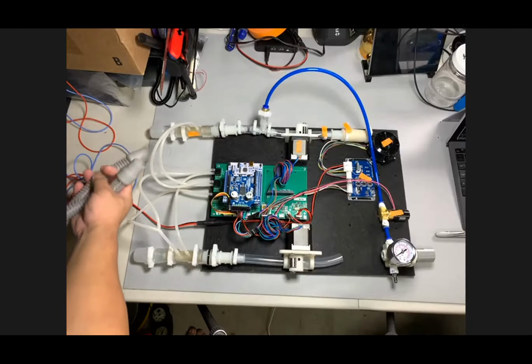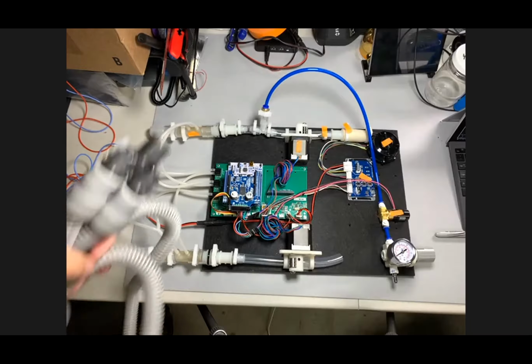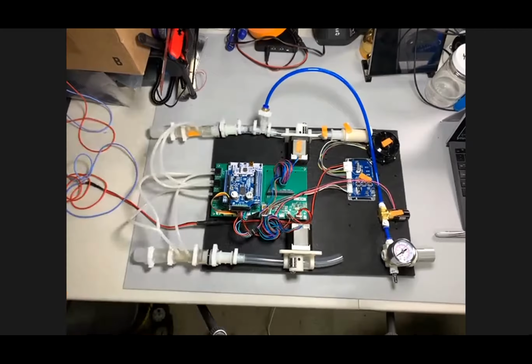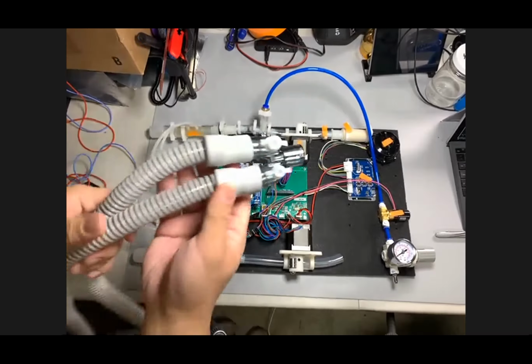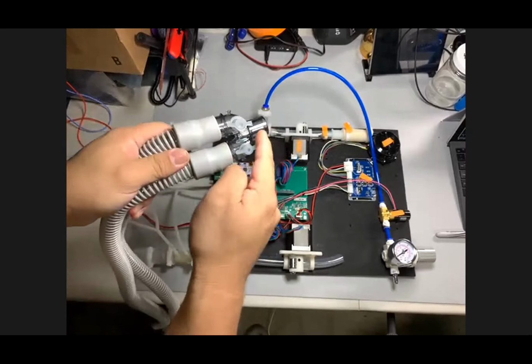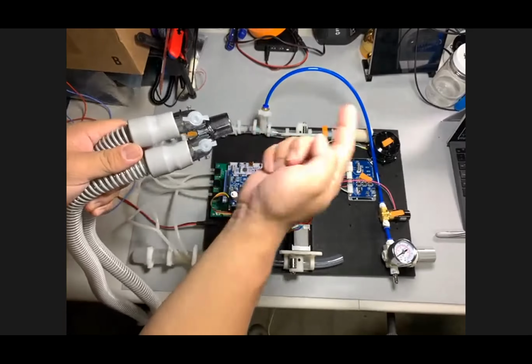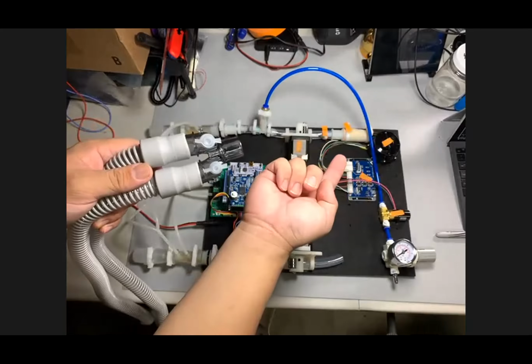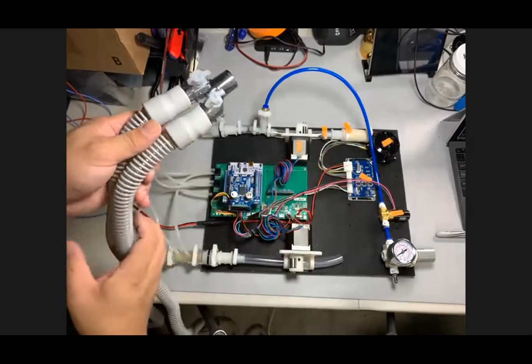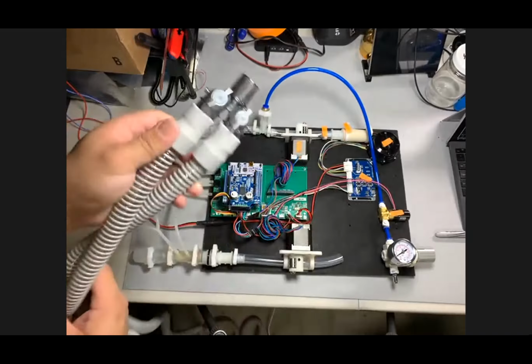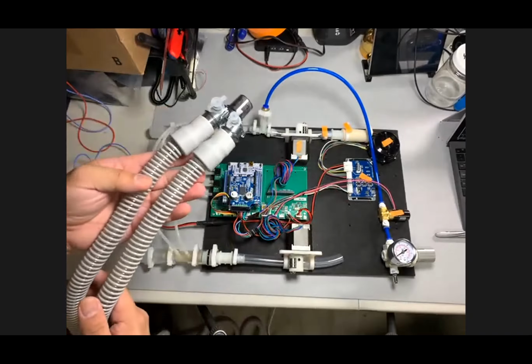Tubing comes in here, it plugs in. This tubing then goes to a Y here. Inlet air comes in here, it goes to the endotracheal tube, which is delivered to the patient's lungs, and then returns here on the expiratory limb. There are no check valves in here, this is just an open flow circuit.